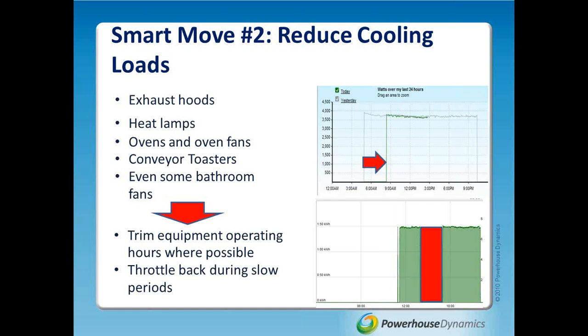One thing we find when talking about hoods drawing out the conditioned air: a quick way to tell if your property has negative pressure is if you really have to tug on the door to open it, almost like there's a suction keeping it closed. That means the restaurant is sucking in as much air as it can to fill the space, because the hoods are piping it out the top.